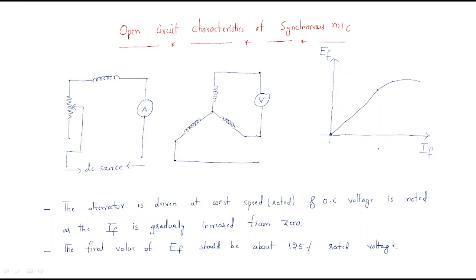By varying the field current, we collect the voltage reading from the voltmeter — this voltage is the induced EMF, Ef. The relation between the field current and the induced EMF gives the open circuit characteristics. When armature terminals are open, a graph between the terminal voltage and field current gives the open circuit characteristics.